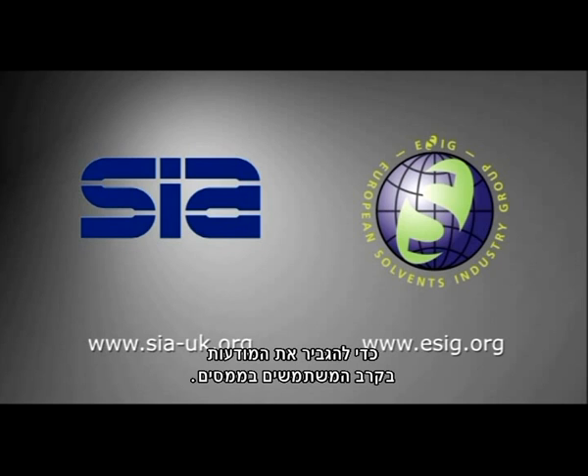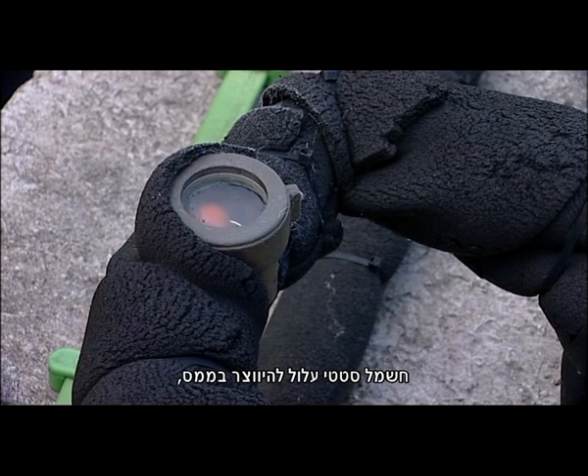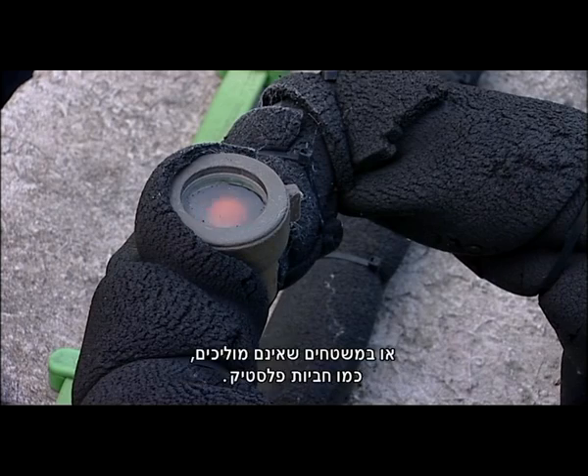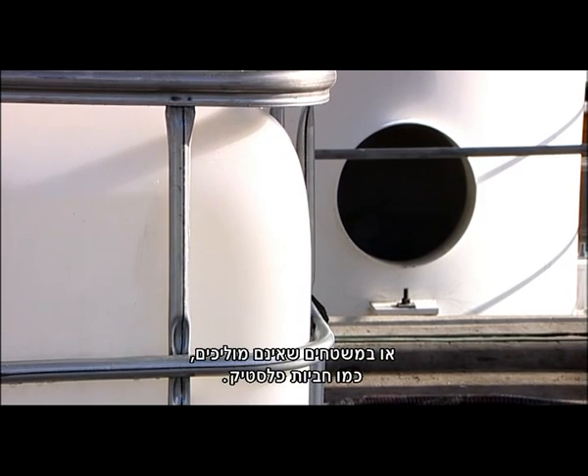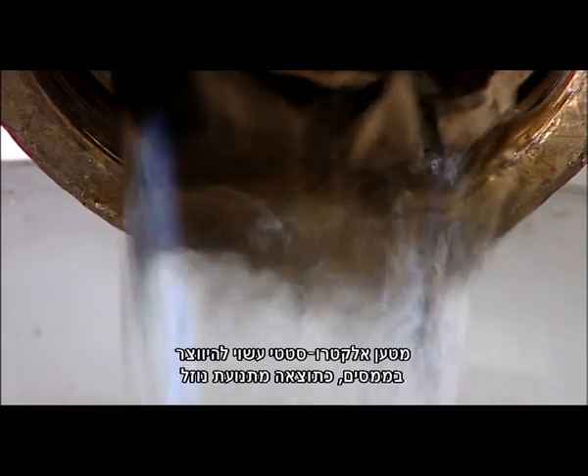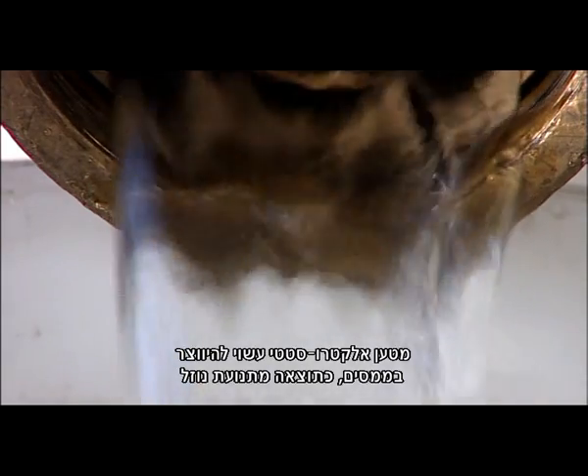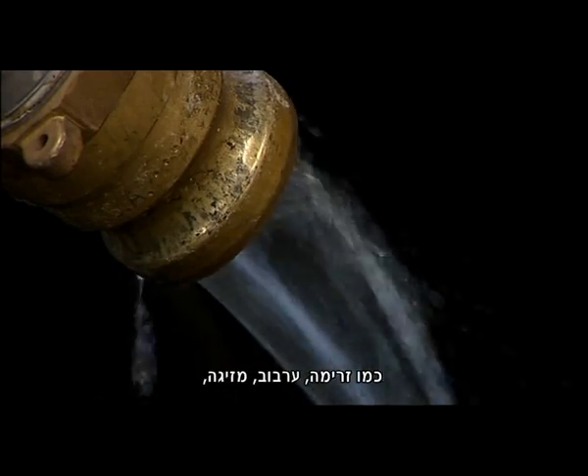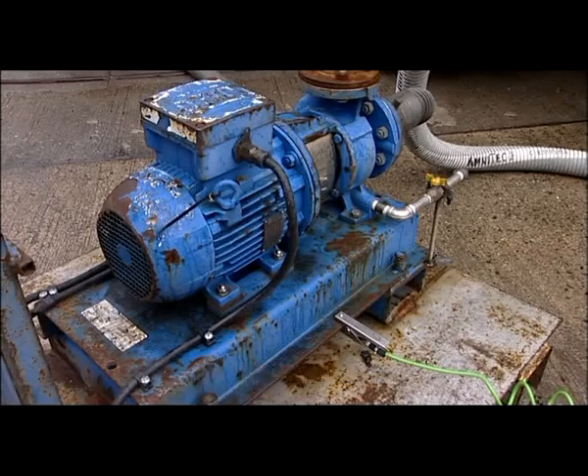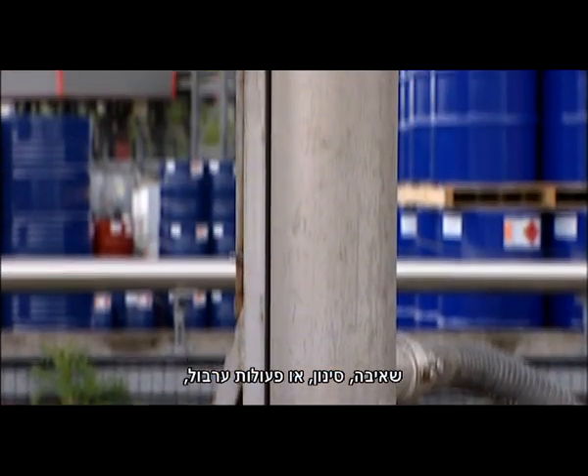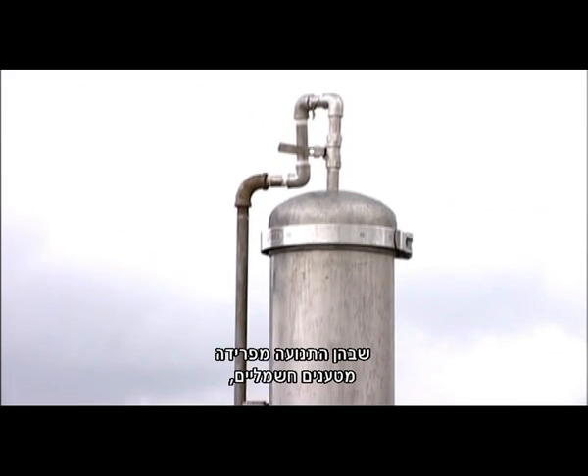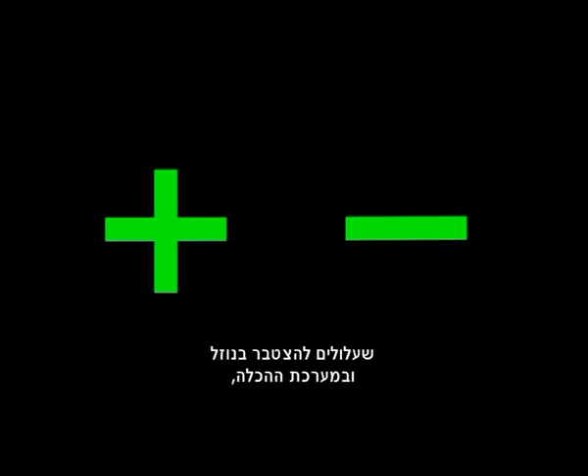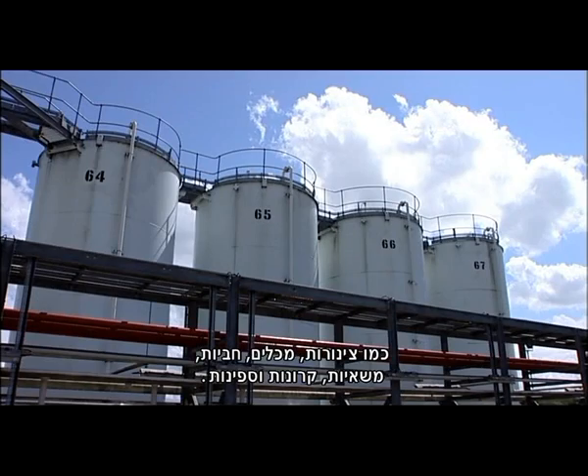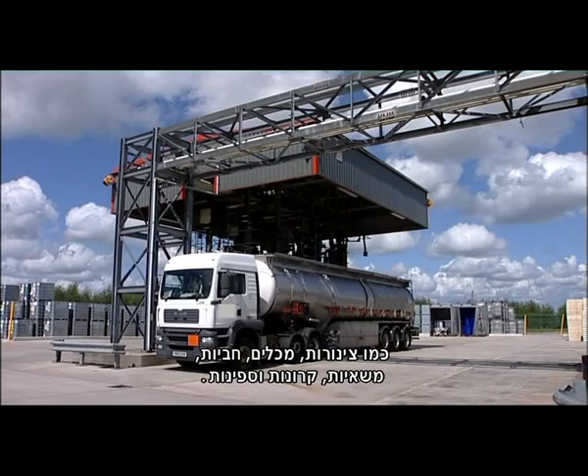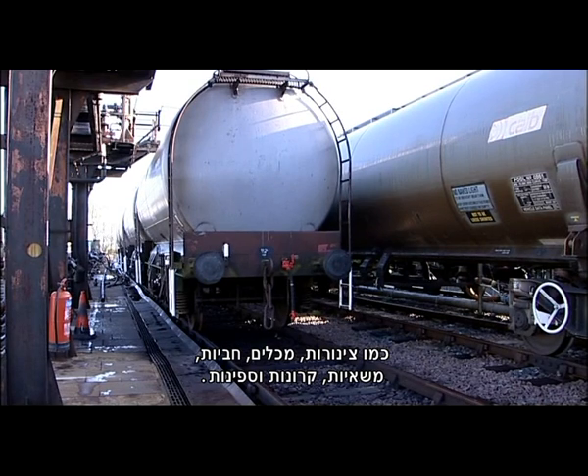awareness among solvent users. Static electricity can be generated in the solvent or on non-conductive surfaces such as plastic drums. Static electricity charge can be generated in solvents by liquid movement such as flow, mixing, pouring, pumping, filtering, or agitation operations, where the movement separates electrical charges which may accumulate in the liquid and the containment system, such as pipes, tanks, drums, road tankers, rail cars, and ships.